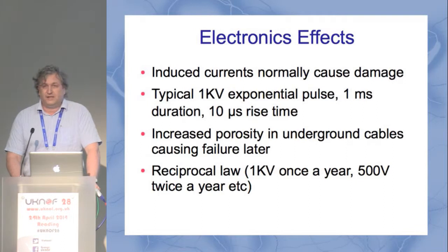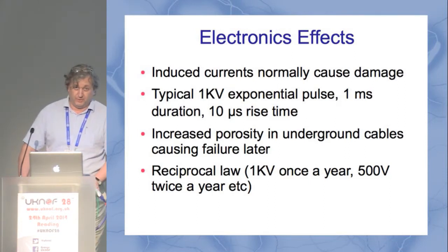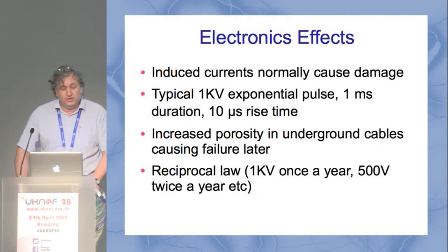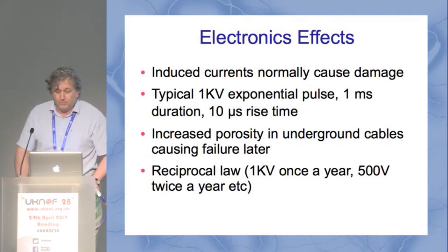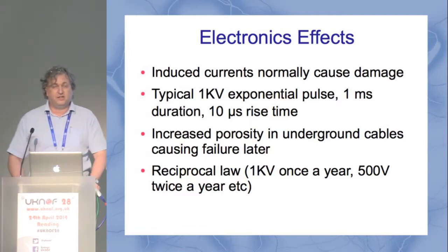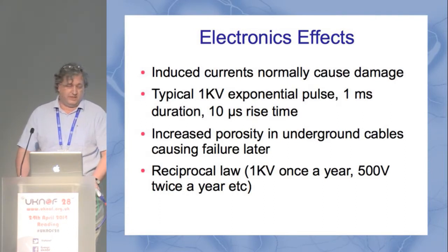Okay, electronics effects, which we're probably concerned about here. It's very, very rarely that a direct hit causes problems. If you get a direct hit to your electronic equipment, well, it's fried anyway, so forget about it. But induced currents actually can cause damage as well, and these are much, much more common. Typically, you will see a 1 kilovolt exponential pulse, about 1 millisecond in duration, about 10 microseconds rise time. And these occur surprisingly frequently in BT lines and so forth.